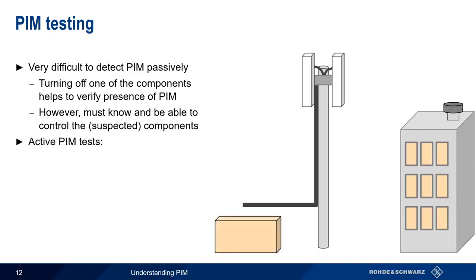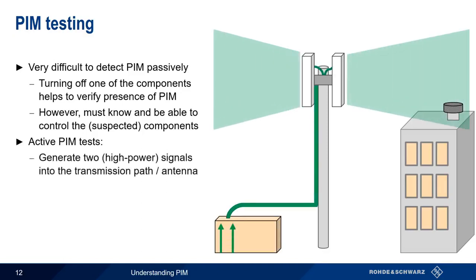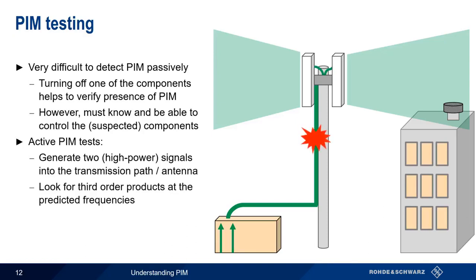A special instrument called a PIM tester is connected to a base station antenna via the transmission line, and two CW tones are injected. The PIM tester knows the frequencies at which third order products would appear given the frequencies of the two tones it's generating. If PIM is being generated either internally within the system or externally, one or both of the third order products will be detected. In a standard PIM test, the third order product is used because it always has the highest amplitude, though higher order products can also cause interference.